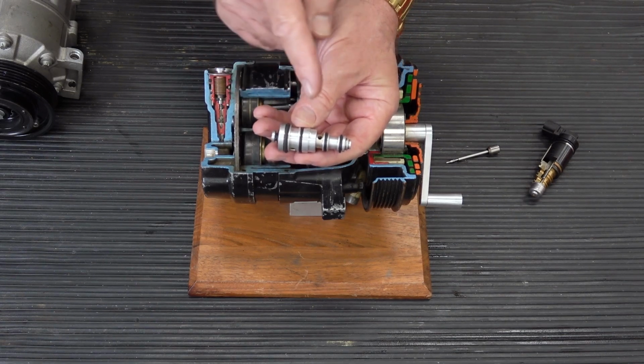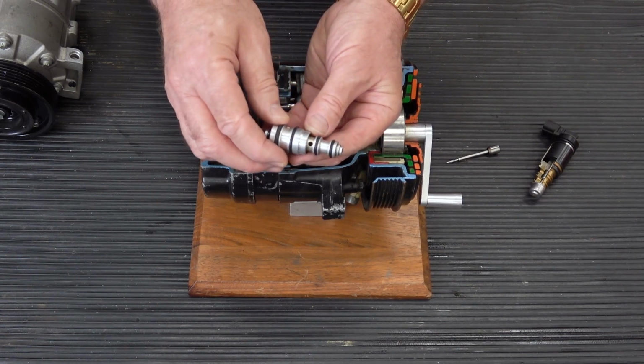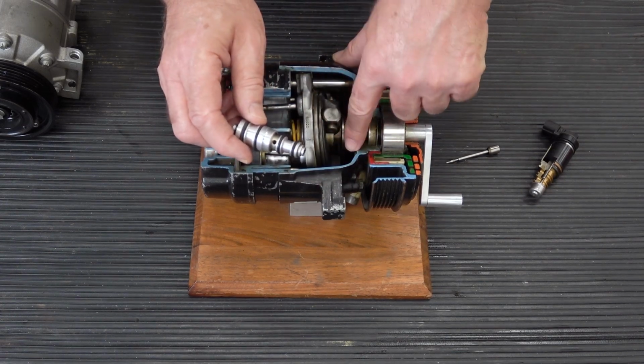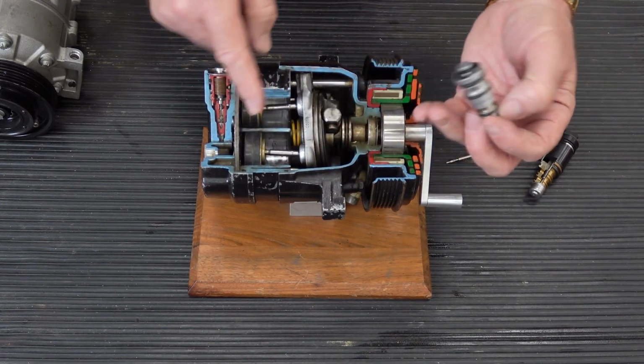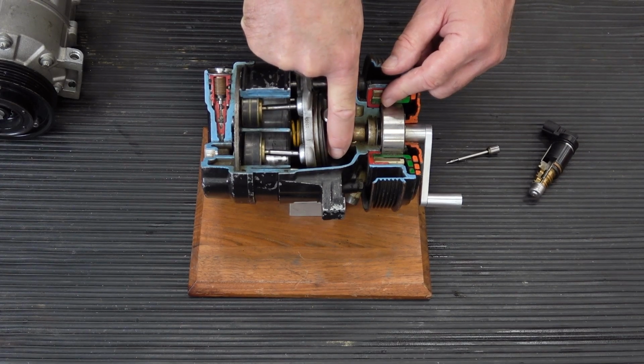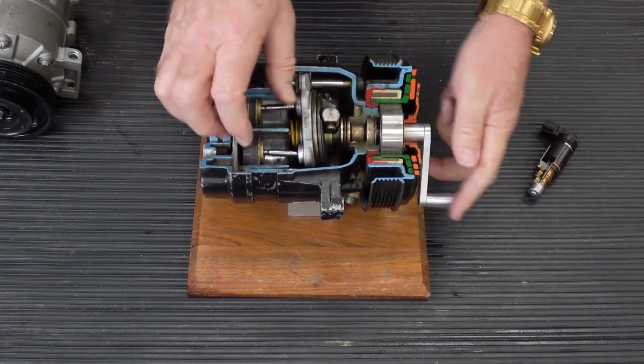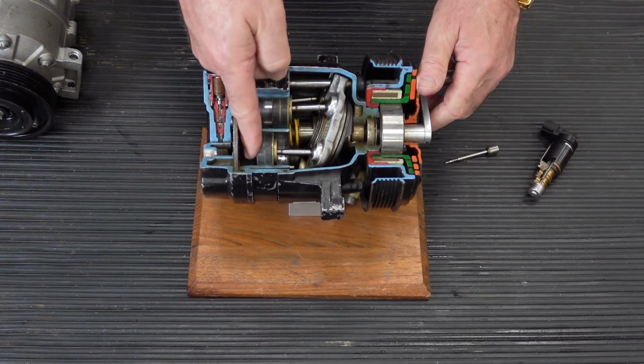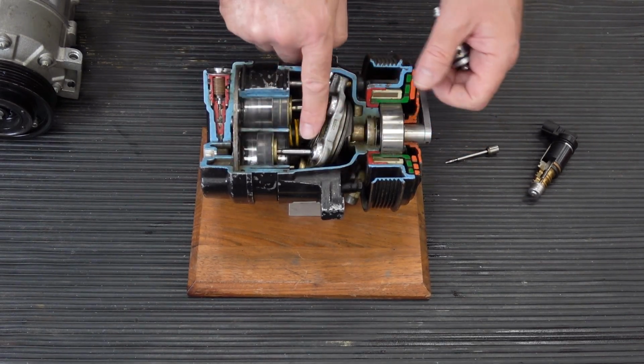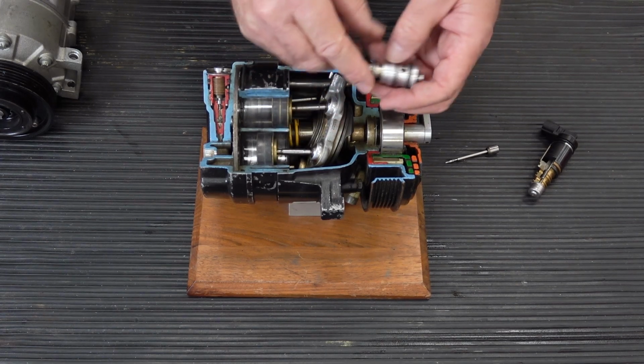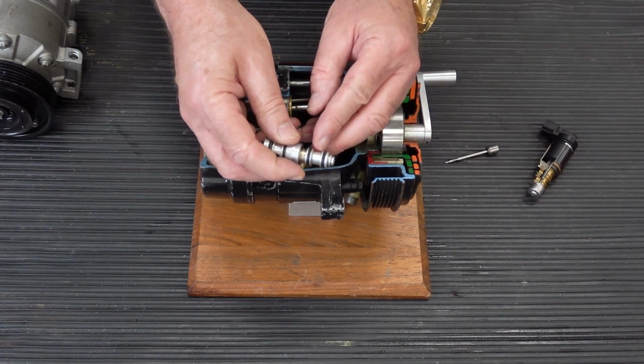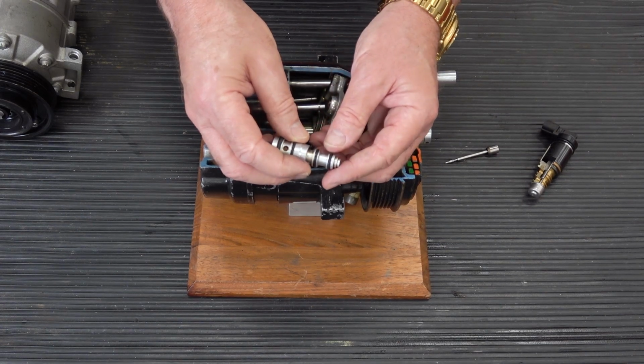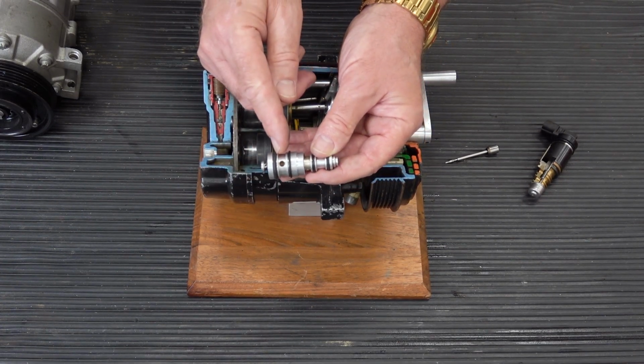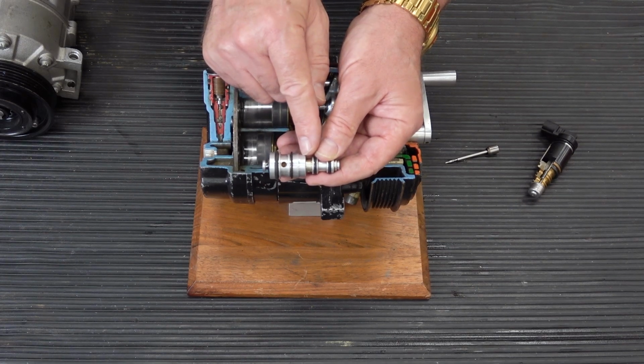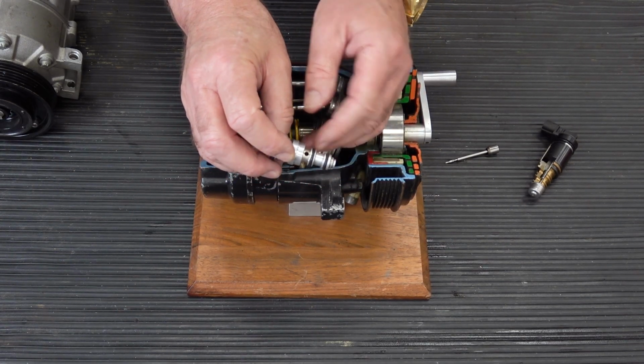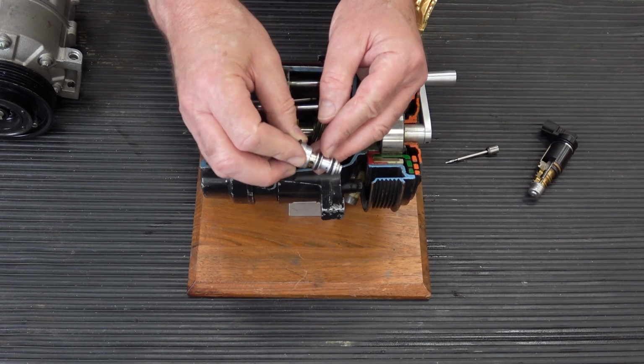And the way this happens is this. The center section of the valve here is exposed to crankcase pressure. In other words, this section of the valve is exposed to the area behind the pistons. Here's the top. This is the top of the piston here. And the very tip of the valve, at the narrow end, is exposed to high side pressure. So I'm sensing suction pressure here, I'm exposed to crankcase pressure here, and I'm exposed to high side pressure here at the very narrow end of the valve.